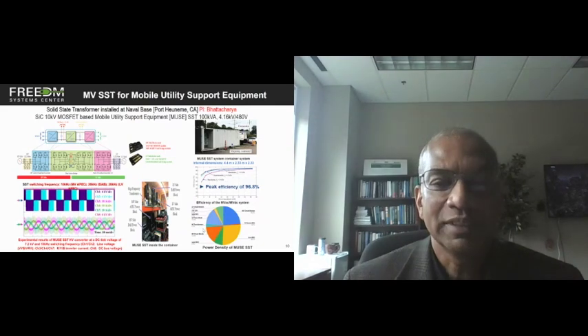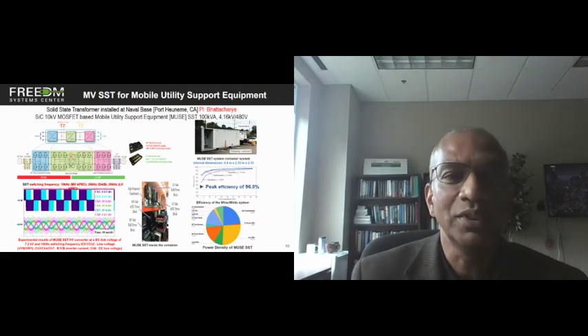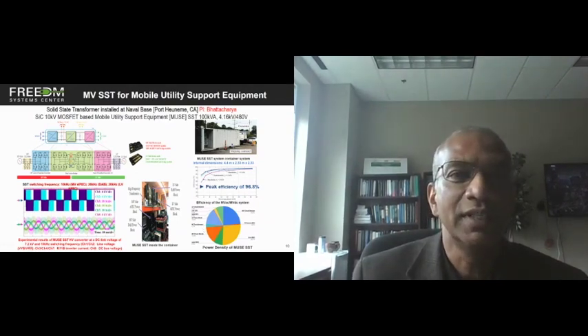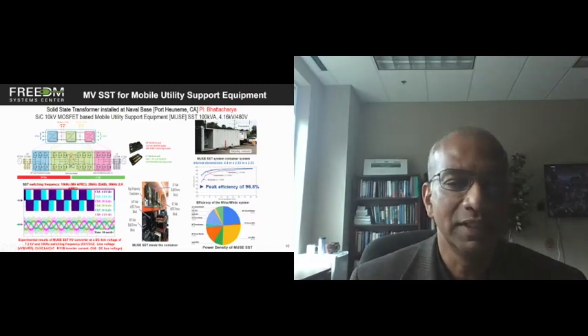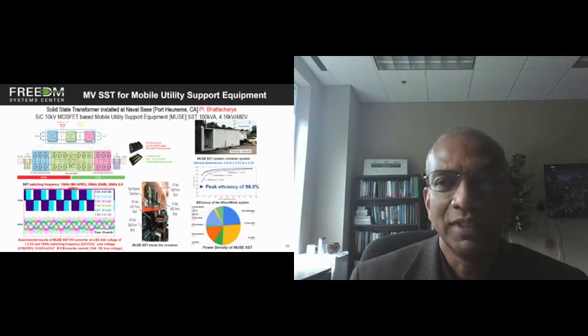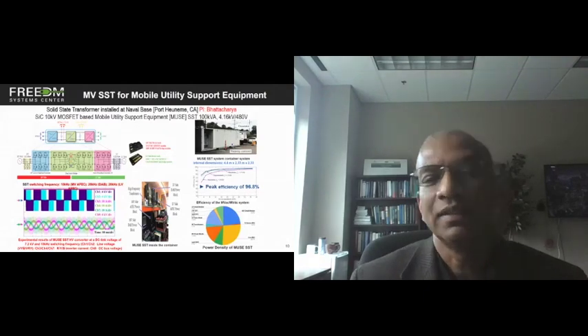The medium voltage SST has been funded by the Navy and installed at a naval base in Port Hueneme, California, for mobile utility equipment use. The SST is based on 10 kV silicon carbide MOSFETs operating at 7.2 kilovolt DC, and the low voltage side is 800 volt DC, delivering an efficiency of 96.8% at 10 to 20 kilohertz. The capacity of this unit is 38 kilowatts.